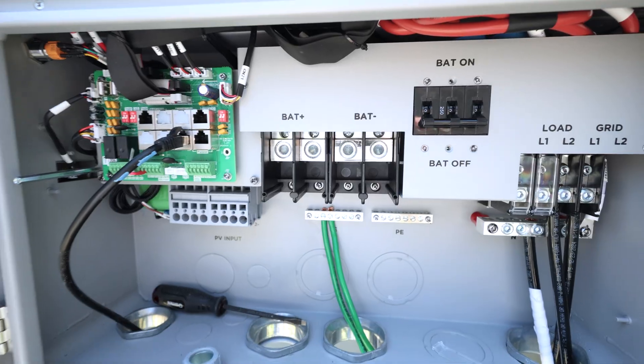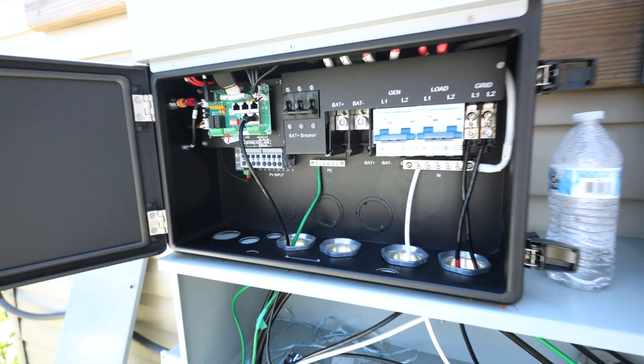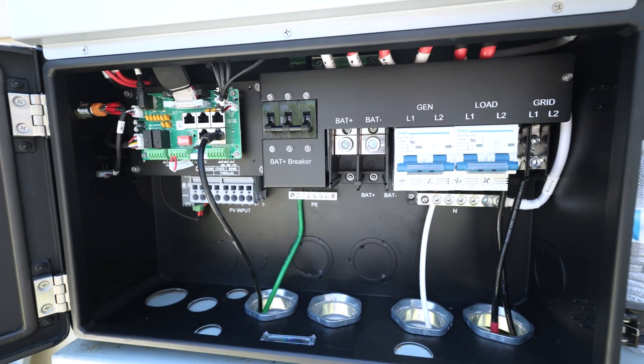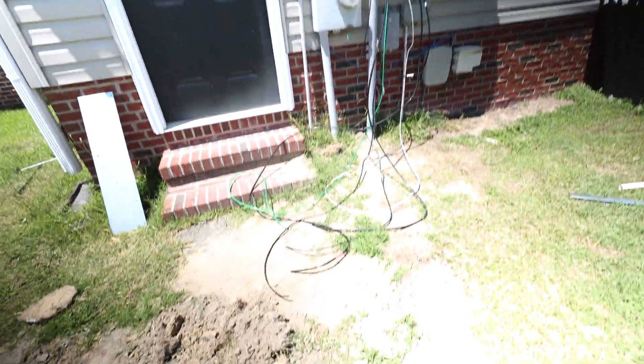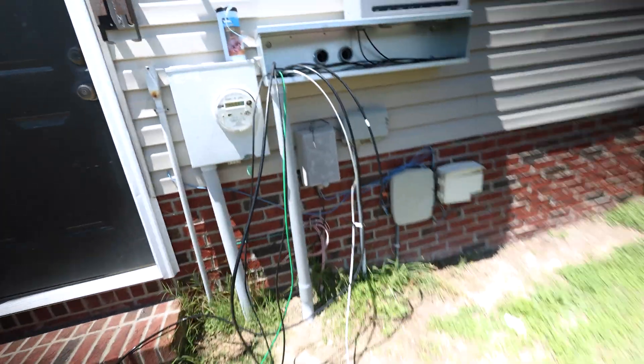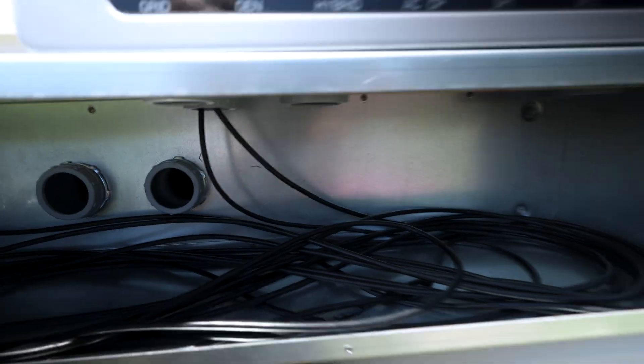These really don't need that size — 2-ought will be fine for what I'm using it for. So I'll use parallel 2-ought over here on the Flex Boss, and then over here on the 12K it's a single pair, going to be a lot less power. Still working all the cables over here — got the cables pulled but don't have them all connected. Got some of the communication cables going up already and connected.